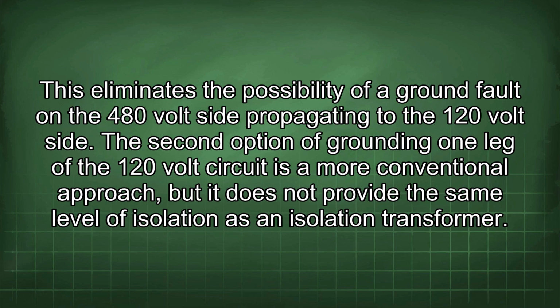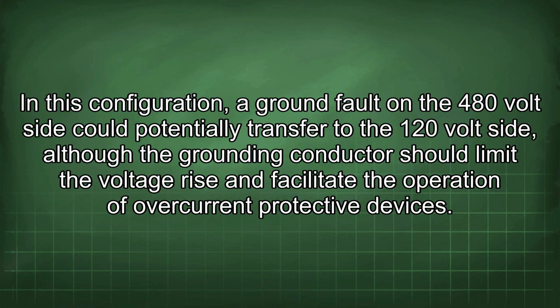The second option of grounding one leg of the 120-volt circuit is a more conventional approach, but it does not provide the same level of isolation as an isolation transformer. In this configuration, a ground fault in the 480-volt side could potentially transfer to the 120-volt side, although the grounding conductor should limit the voltage rise and facilitate the operation of overcurrent protective devices.